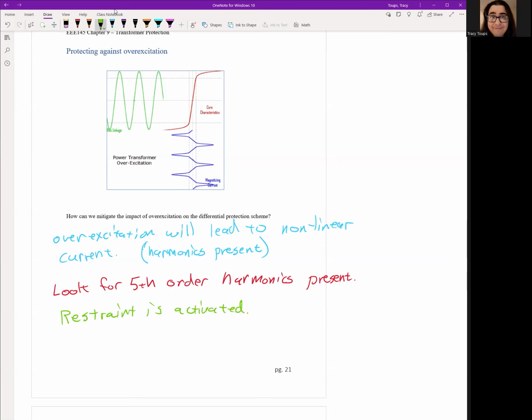This will stop the differential from operating for this temporary overvoltage. Most likely we'll send an alarm out to the operator so they can dial back the voltage. After a certain time, if this doesn't get resolved, then we'll probably trip the circuit breaker and take the transformer out. This is called a fifth harmonic block, and it's typically set to about 35% on the SEL relays.